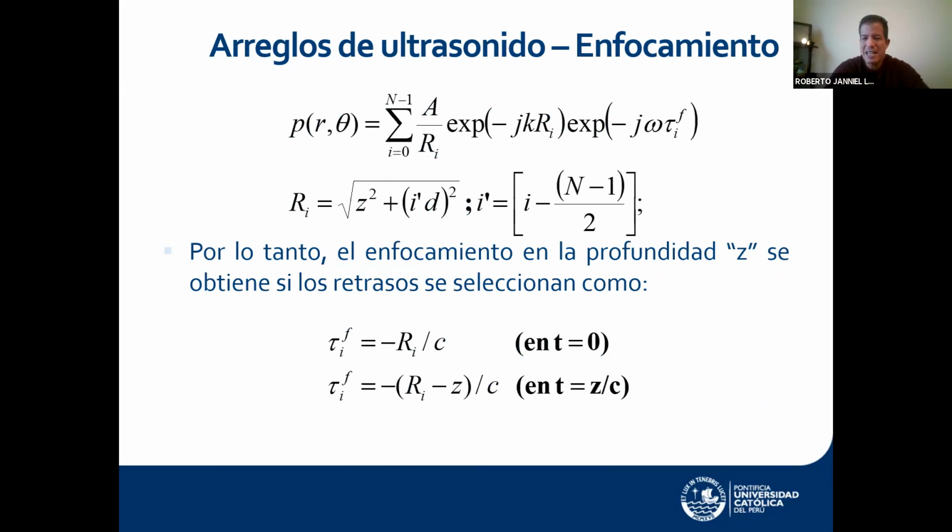What did we need in order to focus an ultrasonic beam? What we said that we needed was we grab the transducer and we curve it so that every point in the transducer is at the same distance away from one location that we call a focal point, right?